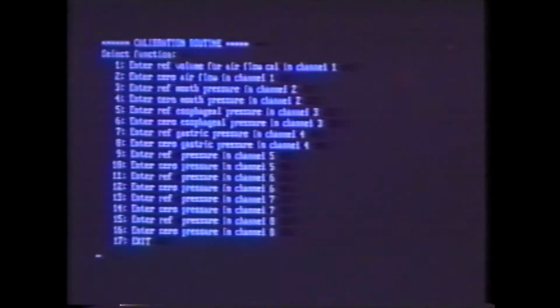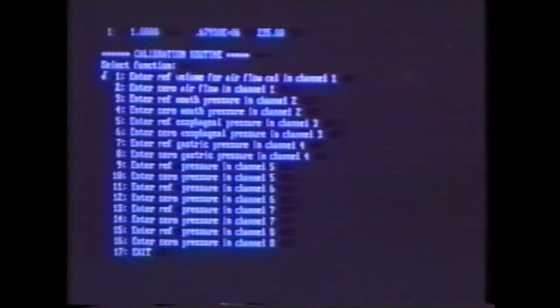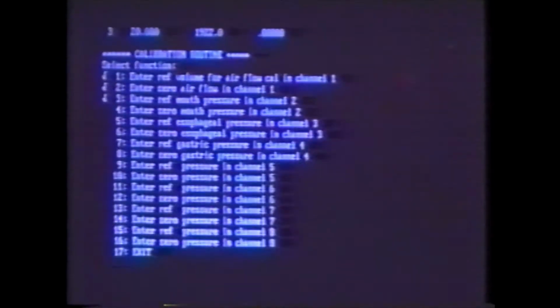Calibration of the mechanical parameters is performed in a separate program where each parameter is calibrated separately. The calibration for each channel is performed in 2 simple steps. For example, in the calibration of flow, which is integrated to volume, the first step is to input a known volume into the system at a relatively constant flow as a reference. Second, a zero flow sample is taken. For pressure signals, first, a signal for a known pressure is input into the system. Second, a zero mouth pressure is selected.